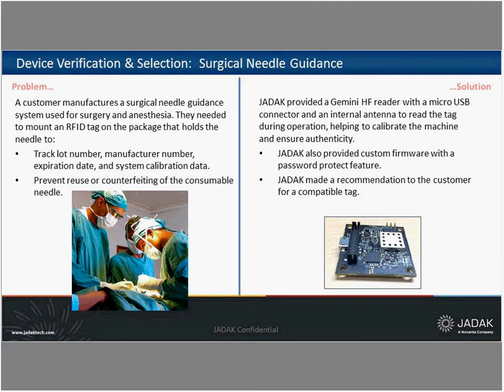The process was to read an RFID tag placed on the outside of the plastic tray which housed the needle used in the procedure in conjunction with an ultrasound device, which was used for guidance of needle insertion. So tag information was used both to calibrate the ultrasound device and to prevent reuse of the same needle.